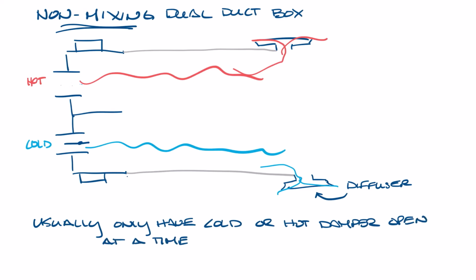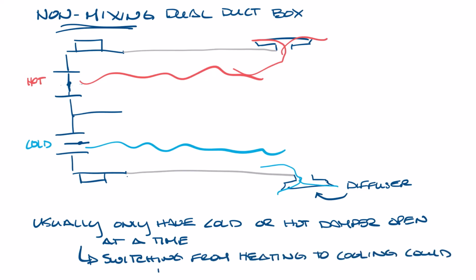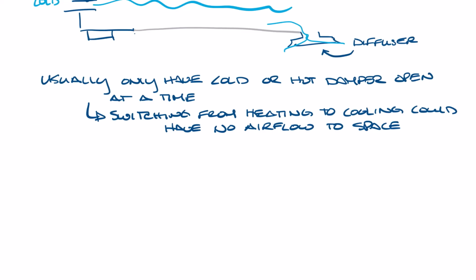So let's delete this hot air damper and now close it. So in cooling, the damper of the hot duct would be closed and the cold damper would modulate to maintain comfort. And then in heating, the reverse would happen, where the damper of the cold duct would close and the hot air damper would modulate. It's also important to note that when you're switching between heating and cooling modes, there can be a moment when both dampers are closed and no air is coming into the box, and so no air is going into the space. Now let's make room again.